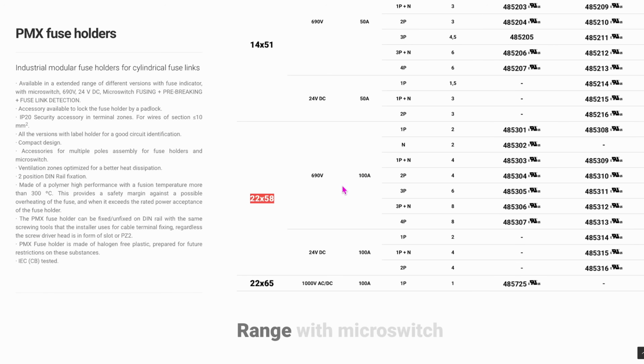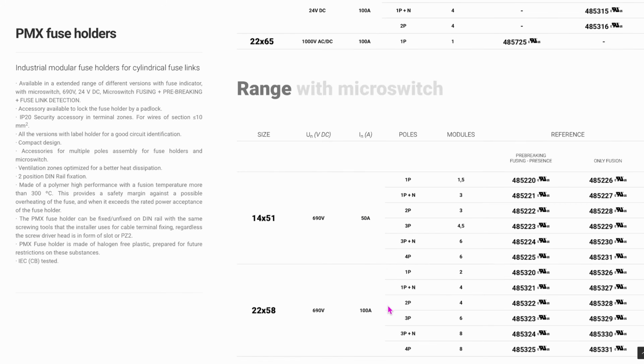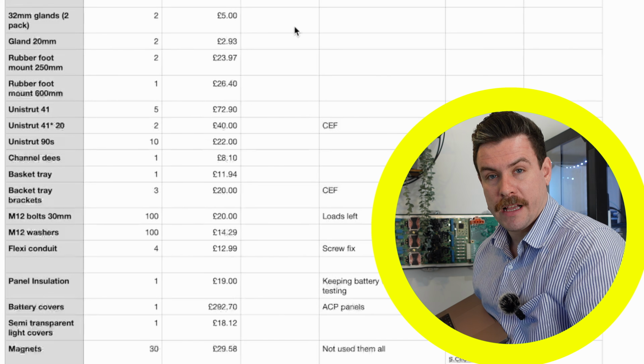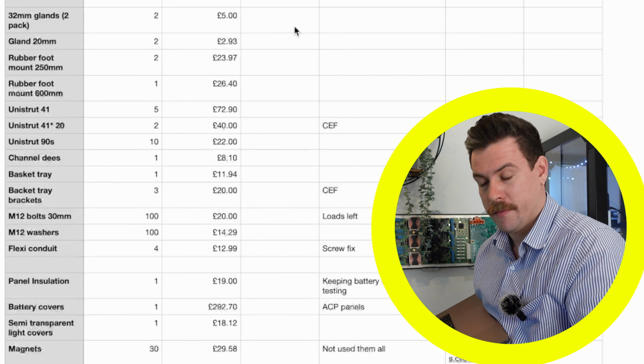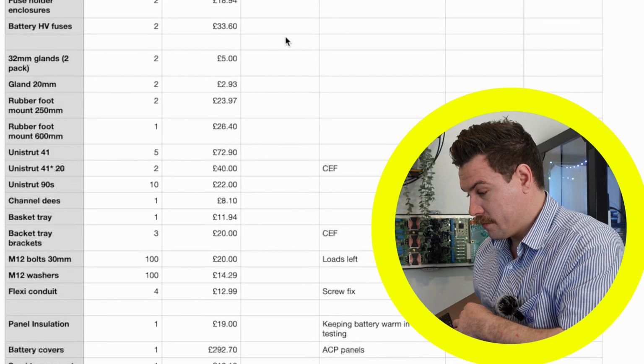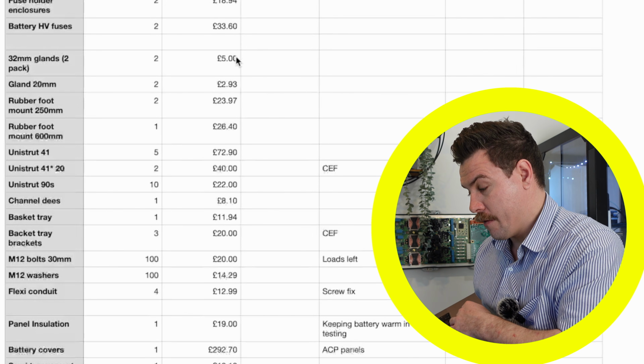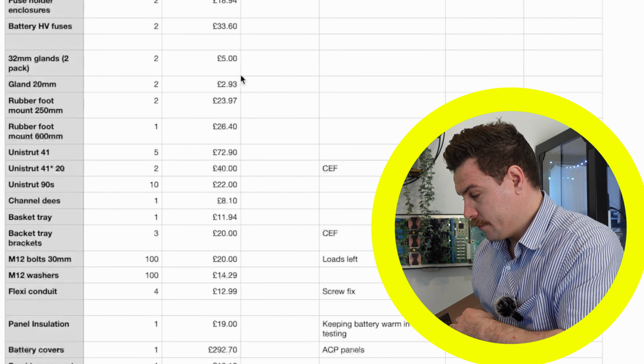Despite pulling 50 amps from the inverter and back and forth, if you run a 50 amp fuse at 50 amps it's only rated to do that for a couple of hours, so you overrate it. But it's still plenty to have the cables protected.